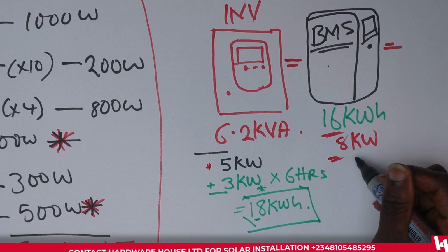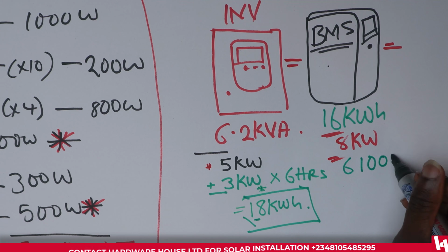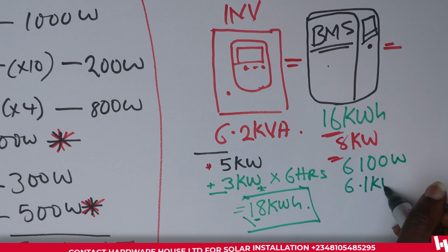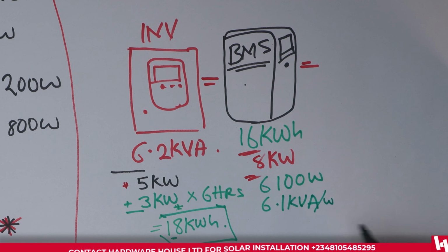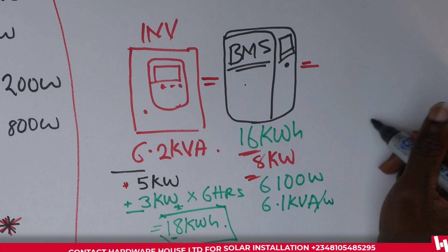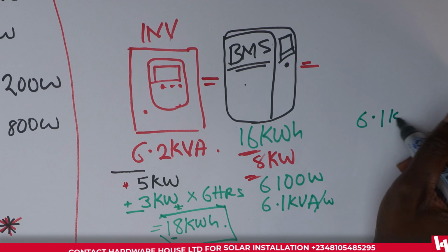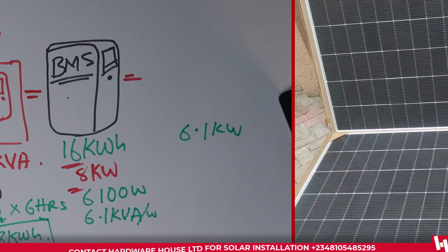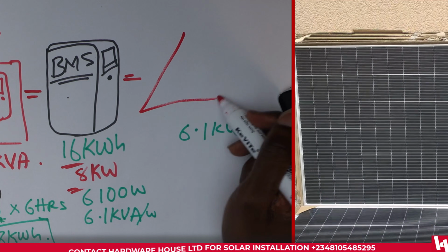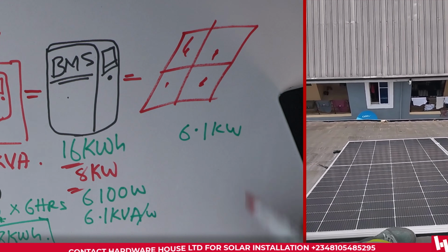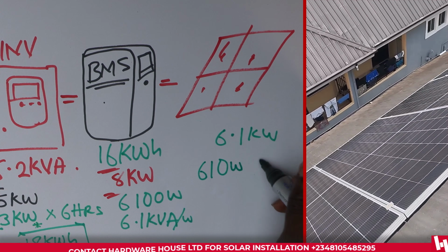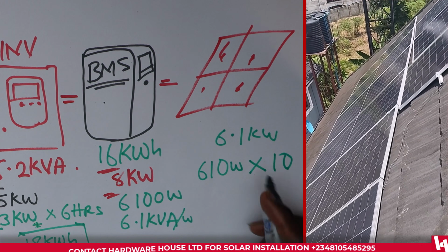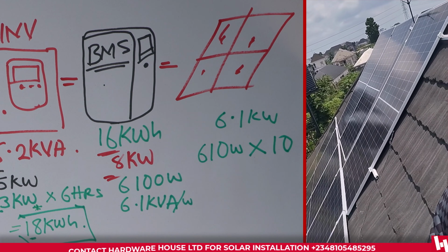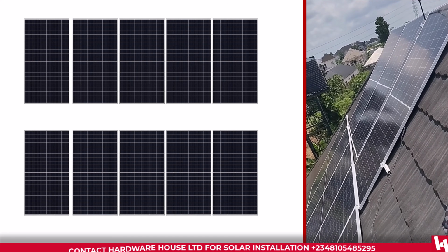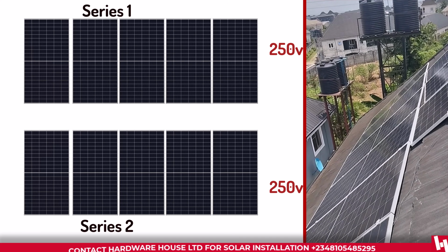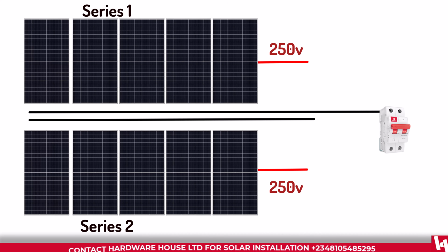So we stepped down to around 6,100 watts of solar panel, which is 6.1 kVA or kilowatts. So we're able to achieve this 6.1 kilowatts of PV with 10 pieces of 610 watt solar panels. That is 610 watt solar panel times 10. And then for the installation of the solar panel, we had 2 different strings of panels, 5 each, going down to the breaker and then to the inverter.